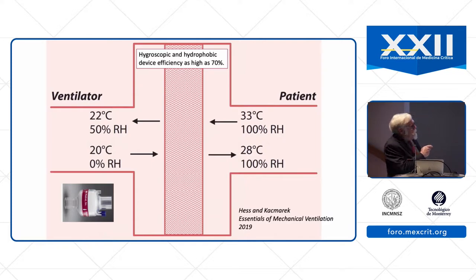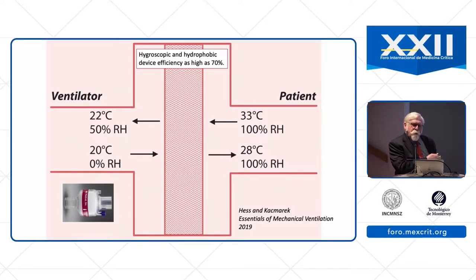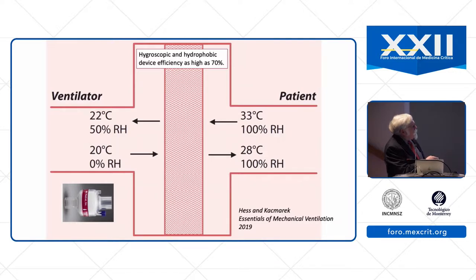Another way to warm and humidify the inspired gas is by using a passive humidifier, sometimes called a heat and moisture exchanger or an artificial nose. These devices contain a hygroscopic or hydrophobic material so that when the patient exhales through this material, much of the heat and humidity from the patient is trapped in the device, and that is delivered back to the patient on the subsequent inhalation. The device is placed between the ventilator circuit and the patient — the patient exhales through it, trapping heat and humidity, which then gets delivered back to the patient.